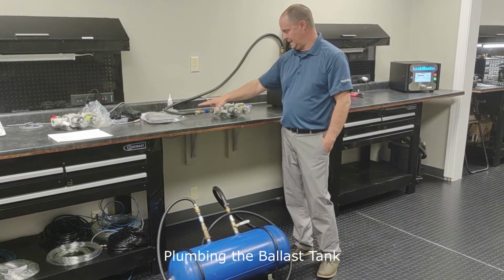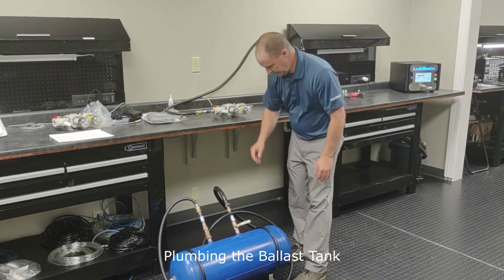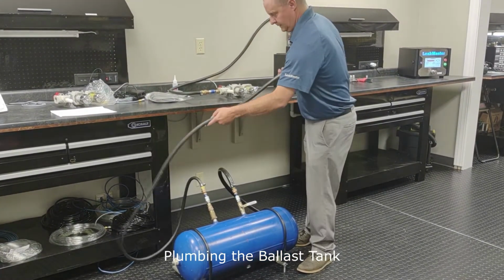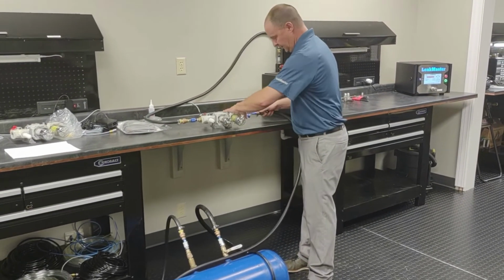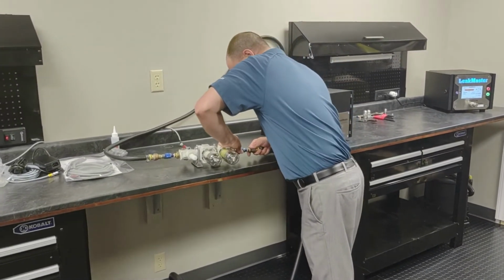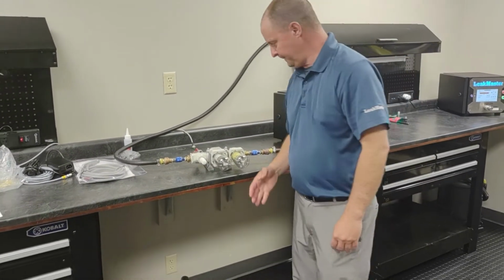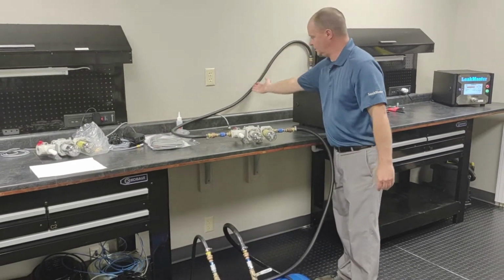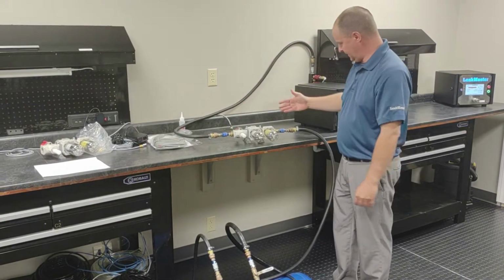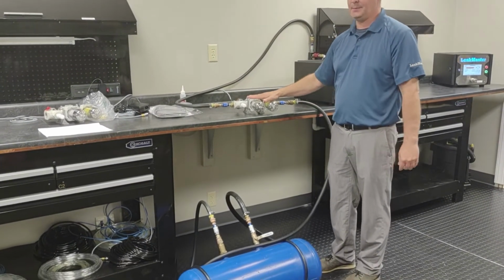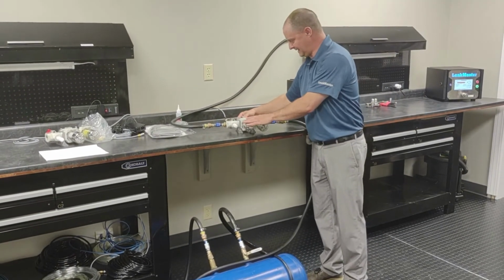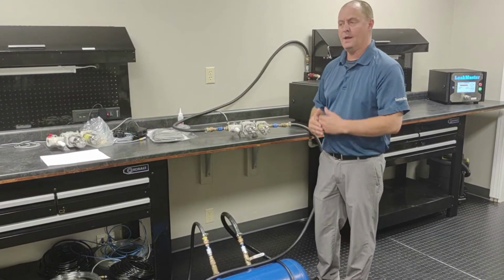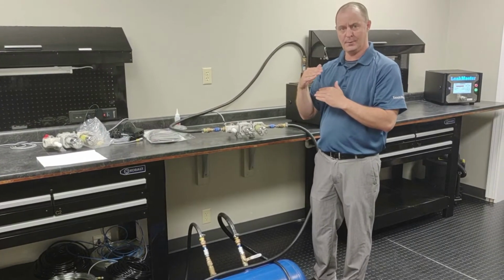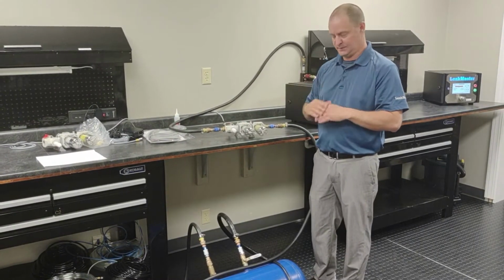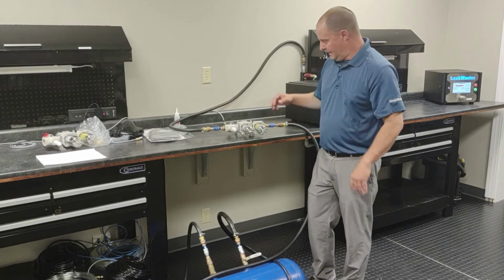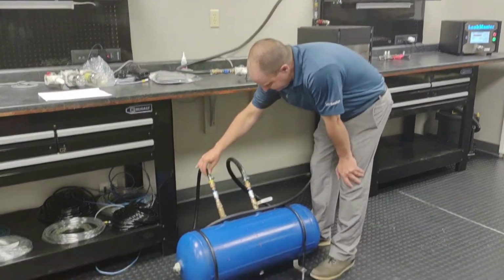Now that we've got the input supply into the air prep unit plumbed in, we are going to come to the output side of the air prep unit, which will feed our ballast tank. Note that I've got 1/2 inch hose coming into the air prep unit and out of the air prep unit, and this is going to be high pressure. More than likely we're going to set this to 60 psi. We want to be well below our line pressure to ensure that we don't have any pressure drops or fluctuation going into our tank. We're going to come out of our air prep unit into our tank.